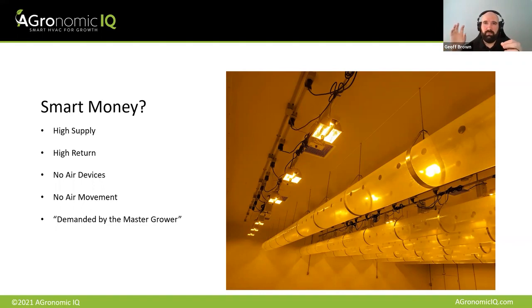So if you have a horsepower of fan in your room, you've now got an extra, call it 3000 BTUs that you have to cool every hour. So there's an energy cost to running the fans, and then there's a second energy cost in cooling the fan energy. But in this case, there are no air rotation fans. There's nothing getting the air to a good part of the room.